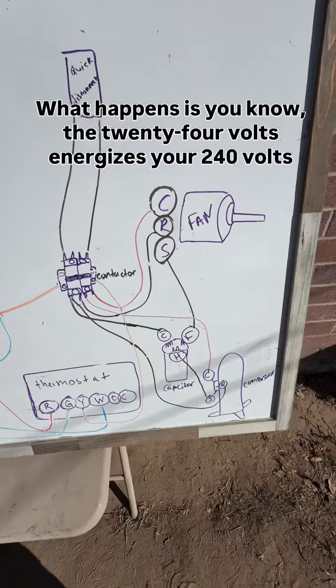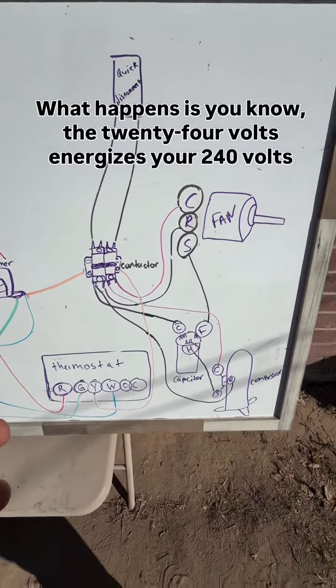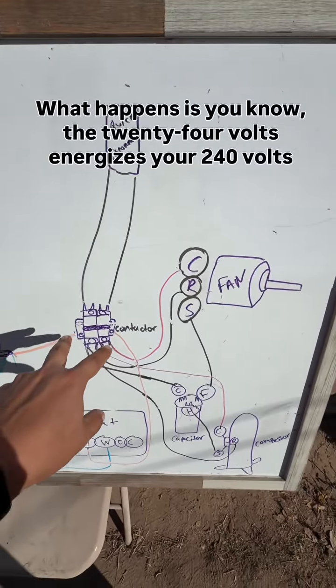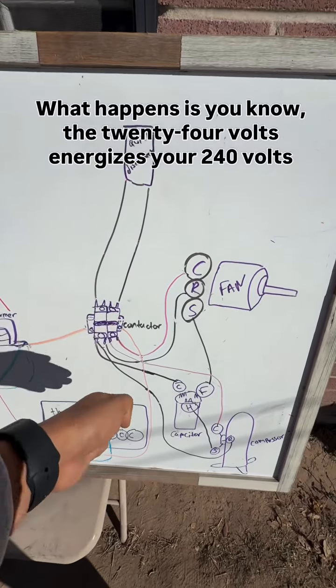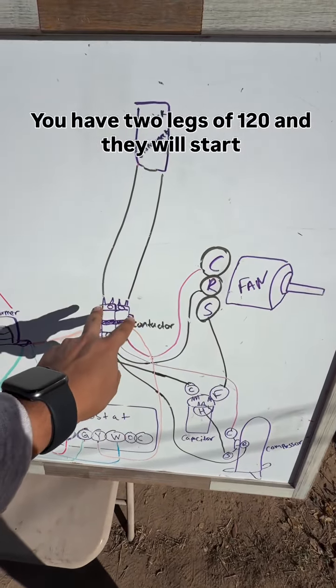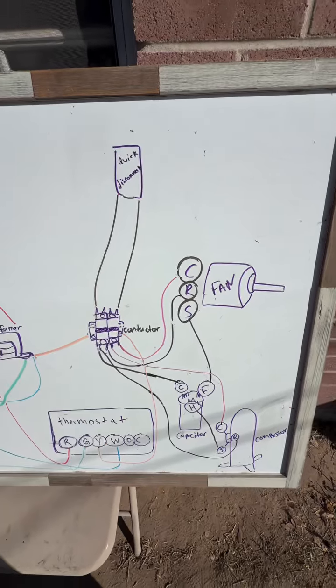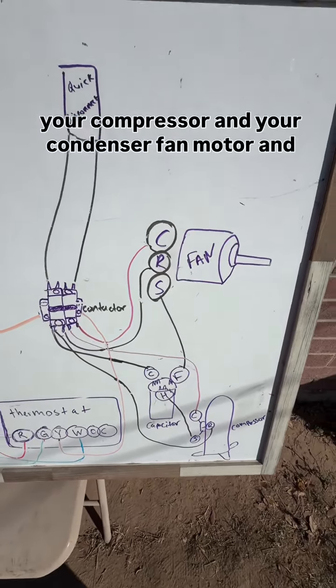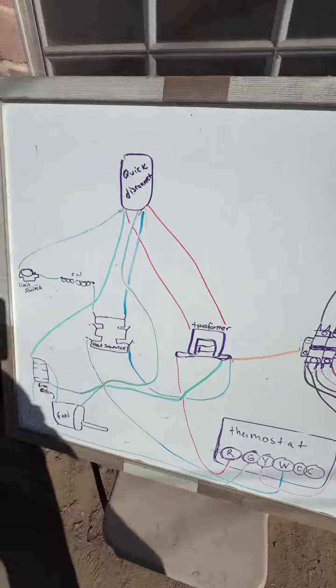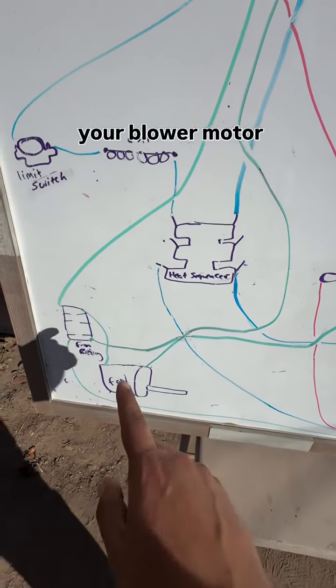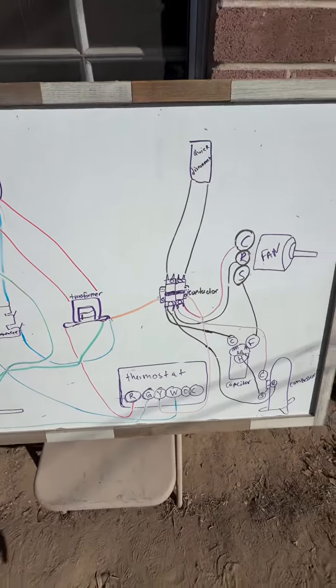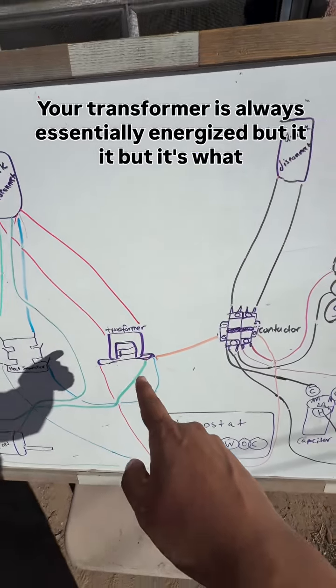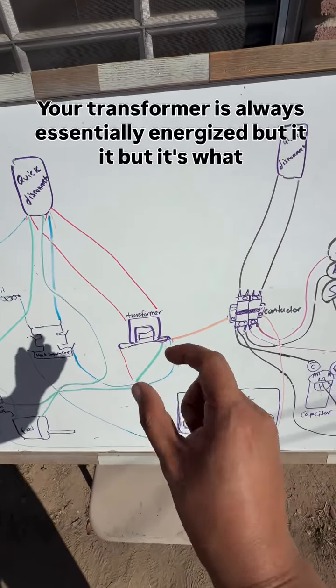Now what happens is the 24 volts energizes your 240 volts. You have two legs of 120, and they will start your compressor, your condenser fan motor, and your blower motor. Your transformer is always essentially energized, but it's what controls the step down.